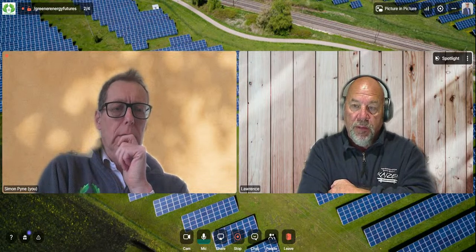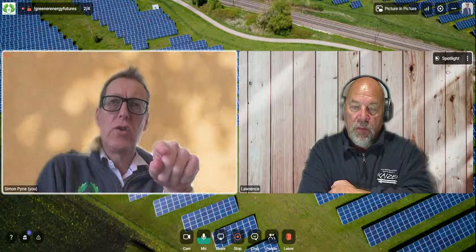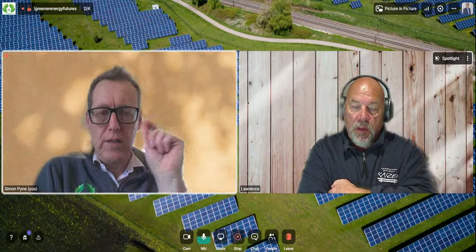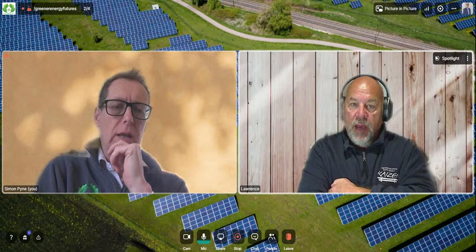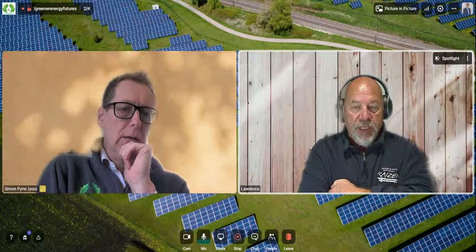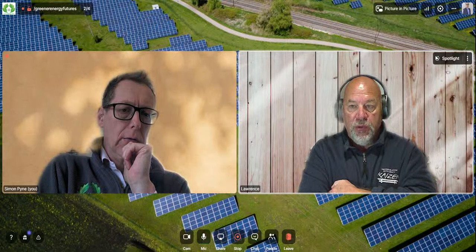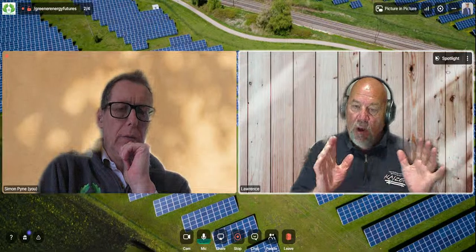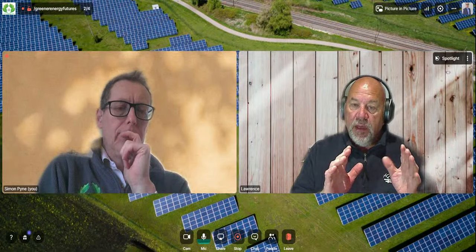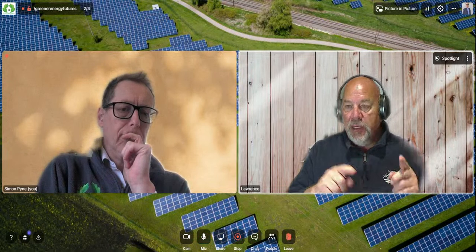But why do you not want insulation on the pipework leaving the building? Is that because you want to disseminate the heat, get rid of the heat? Yeah. Well, for a refrigeration system to work, the first thing you need to do is lose what we call your discharge superheat — that's the high-end heat leaving the compressor — and we can't condense until we lose that superheat.